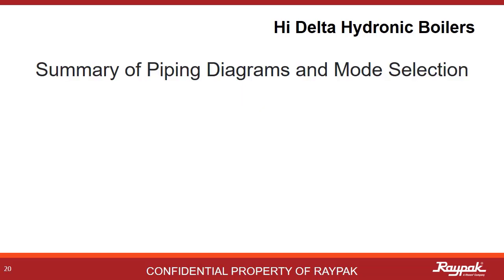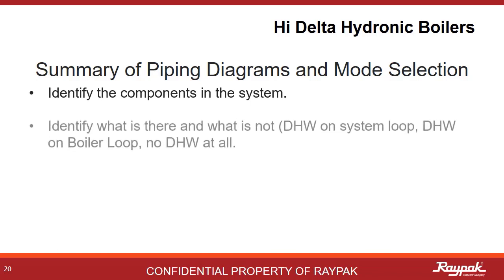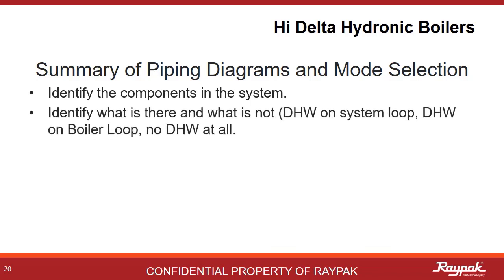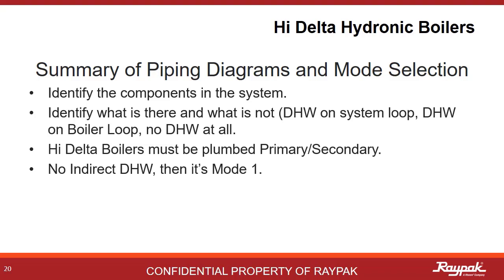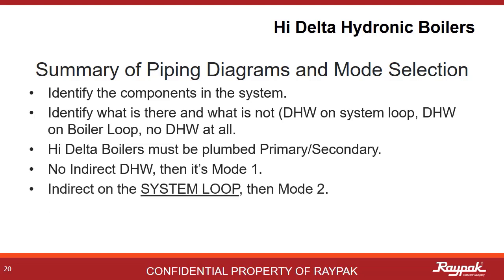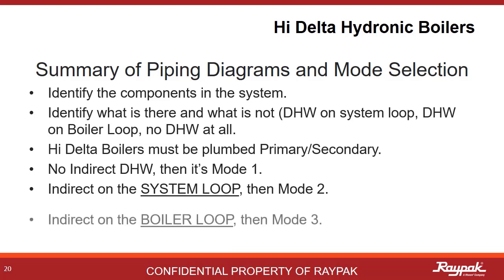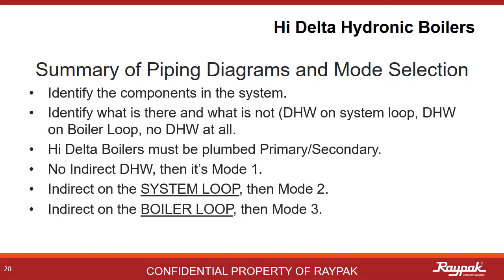Here are some overall pointers on plumbing systems and how they relate to mode selection for type H boilers. Identify all of the parts of the system and look for what is there as well as what is not there. Make sure it is plumbed primary-secondary. In most cases, with no indirect domestic hot water present, Mode 1 will be your choice. If you have an indirect domestic hot water present on the system loop, then it's Mode 2. If the indirect domestic hot water is present on the boiler loop, then it's Mode 3.